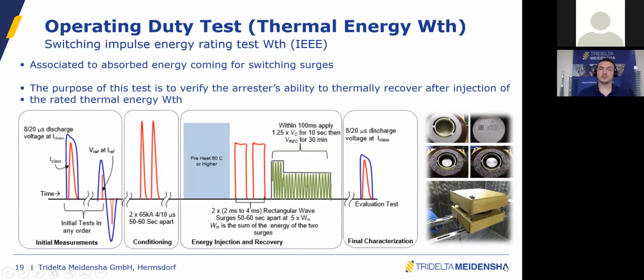Now, I have mentioned the energy ratings before, and one important energy rating is the thermal energy from the type test called operating duty. So utilities have to specify the classification and mention what thermal energy is required on the system. This has mainly to do with switching surges, so basically breaker operation. And it's also interesting because in the IEEE standards in the US, the test is now fully harmonized. Since 2020, there is complete harmonization between IEEE and IEC. And this test is called the switching impulse energy rating test.